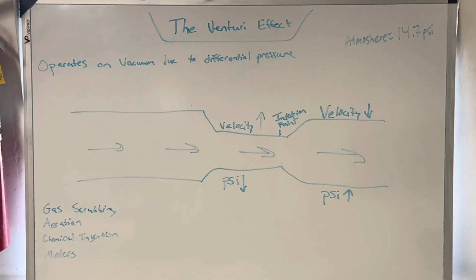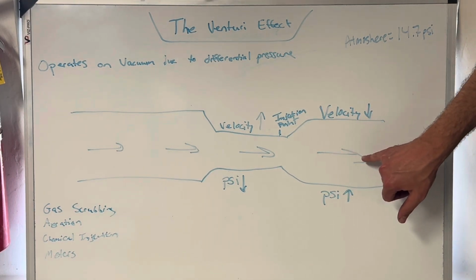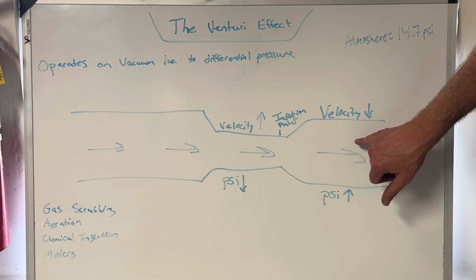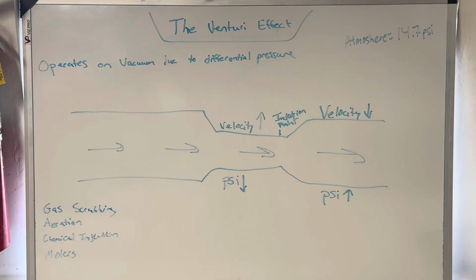What's really cool about Venturi meters is they're very low cost, not a lot can break, and what separates them from other meters is they're able to recover almost all of their pressure, so there's not a lot of pressure loss. And why it's good for wastewater is we have a lot of solids content. You're not going to find a lot of nutating disc meters in wastewater. They get jammed up with crud pretty quick. I actually use mag meters in my plant. I don't use Venturi meters, but it's good for liquids like this.